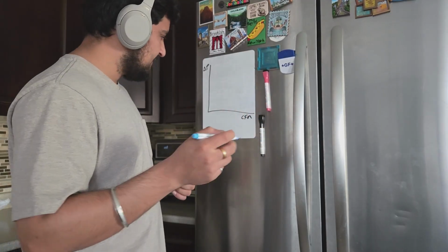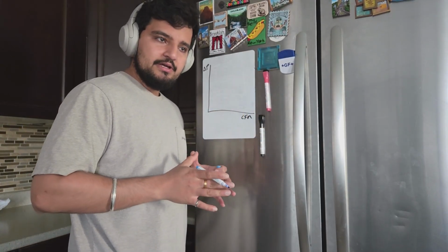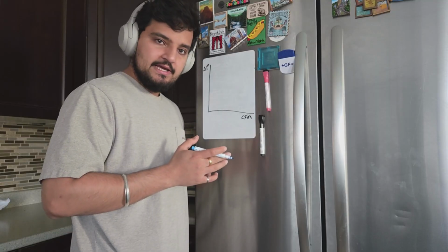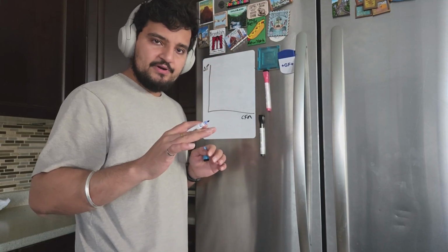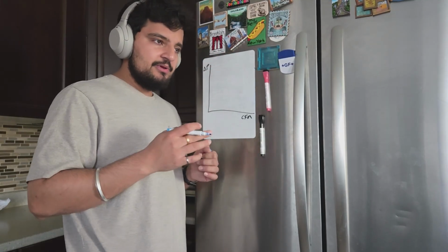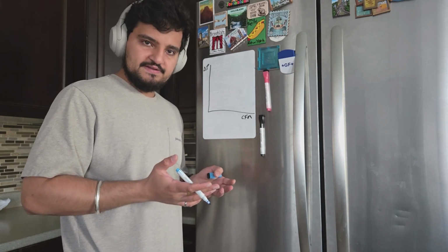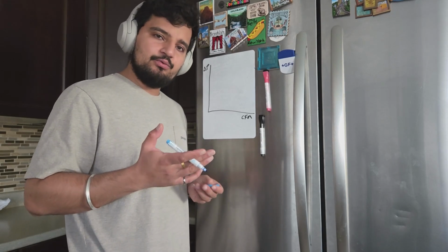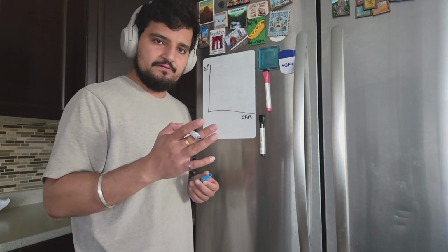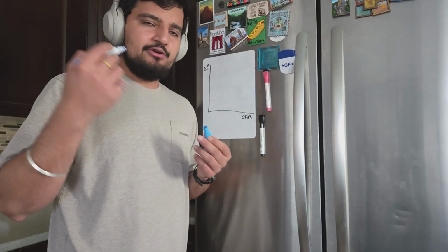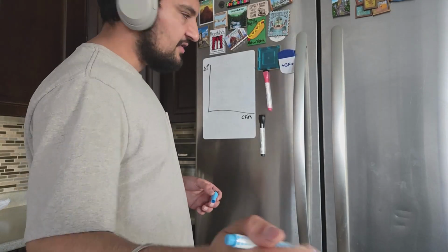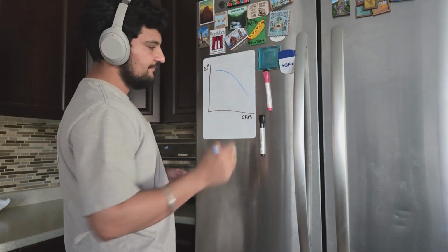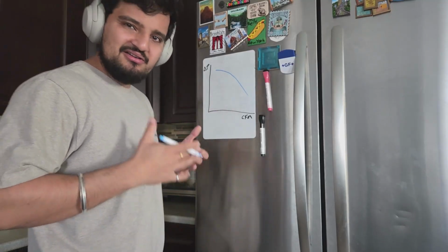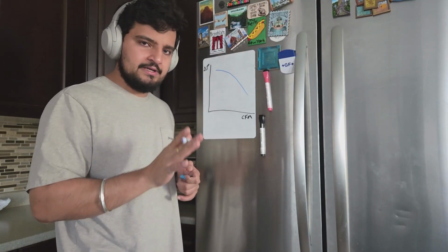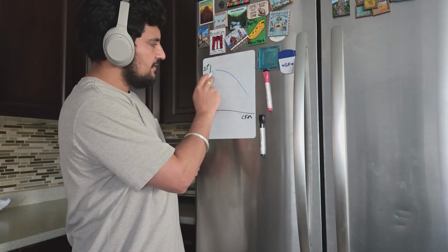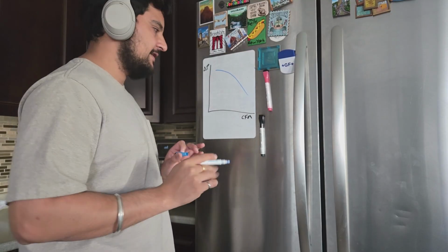We're going to draw what's called a fan curve. So every fan that's manufactured has a curve that it operates on. And this curve is determined through experimentation, essentially. So the manufacturer of the fan will do a bunch of experiments and figure out how this curve looks. It depends on the aerodynamics of the fan. So the fan curve looks something like this usually, right? It's probably not 100% accurate. It looks slightly different for every fan, but the relationship is kind of the same for every fan, right?